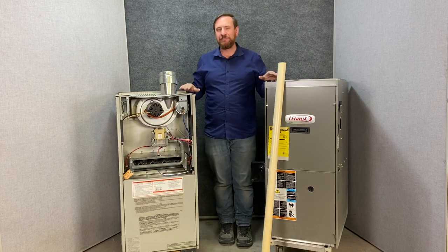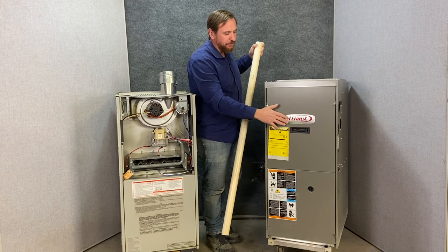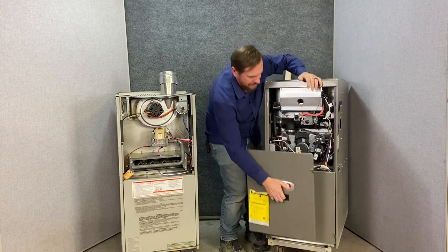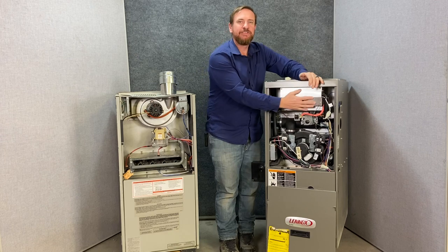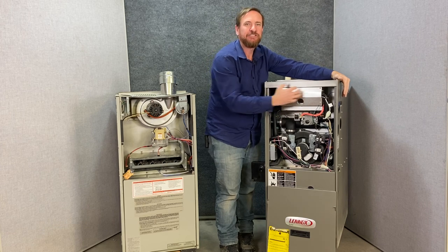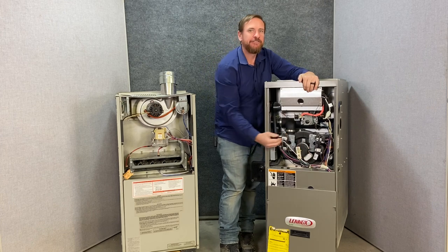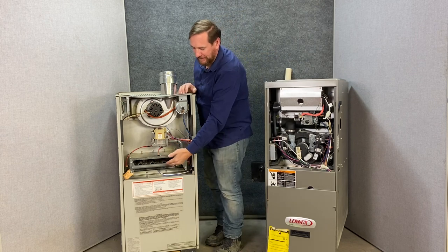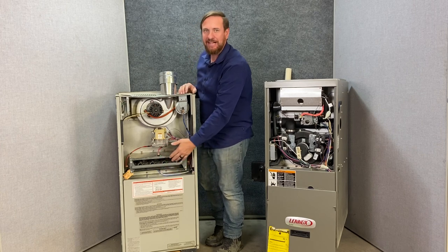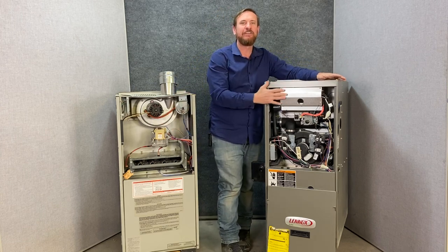These are the big differences between the two furnaces. This 90 plus furnace has a fully sealed door. Inside we can see the combustion chamber — fresh air is piped directly into this sealed box and I can't physically touch the burners or the gas. The inducer fan motor forces that draft back outside. Whereas the 80% furnace is all open: here's the manifold where gas flows, it mixes with primary air, secondary air is around it, and you can access everything. The inducer fan motor pulls it out.